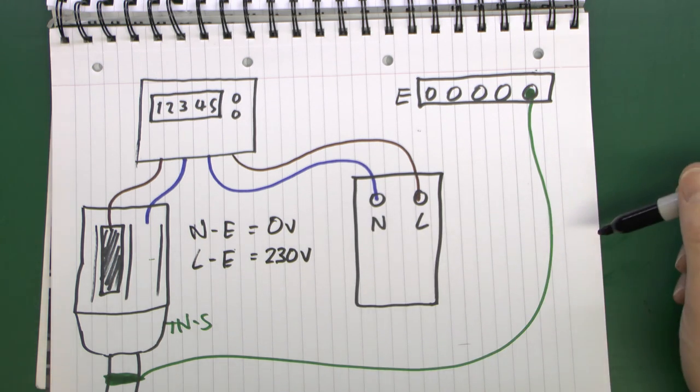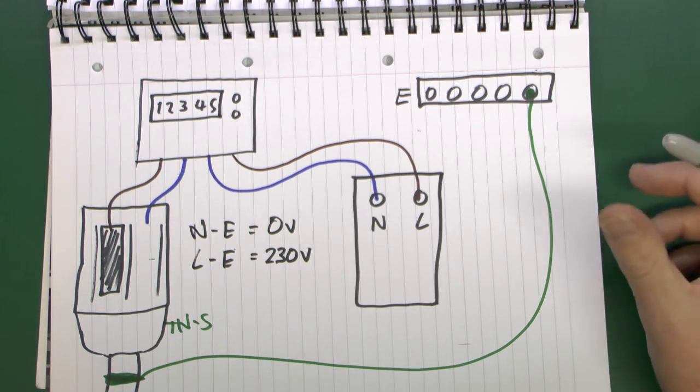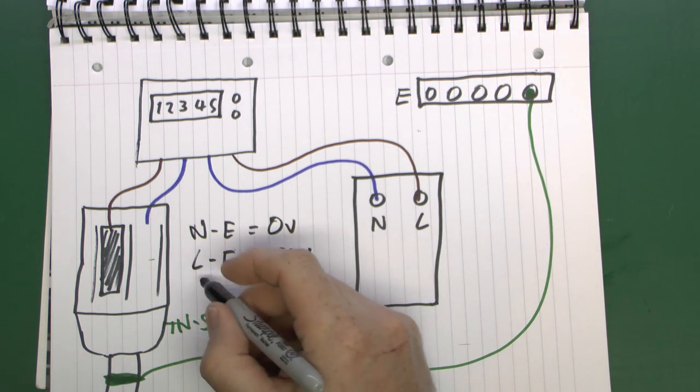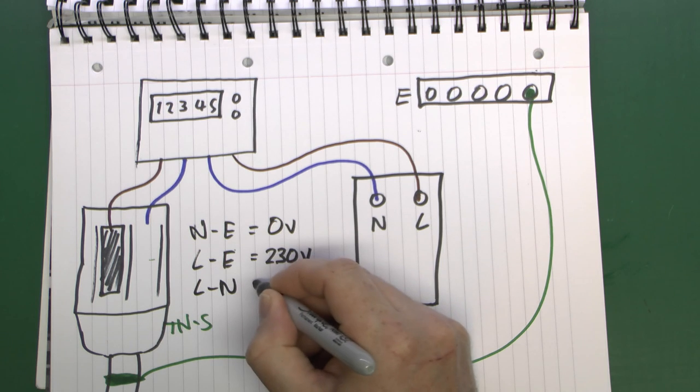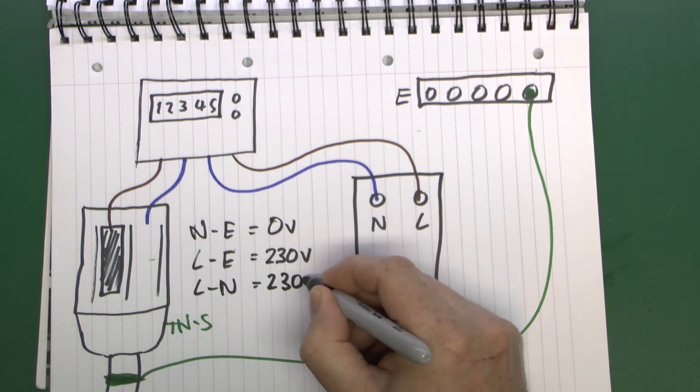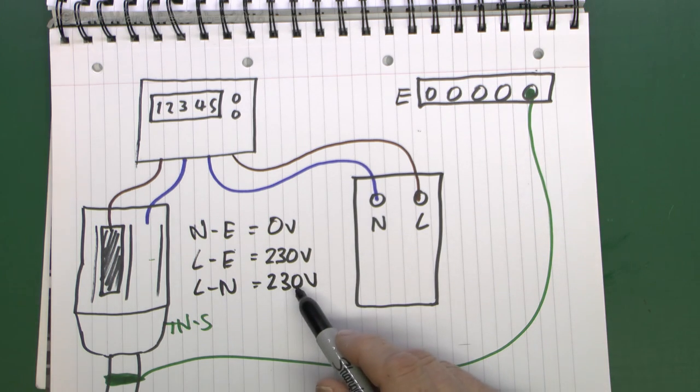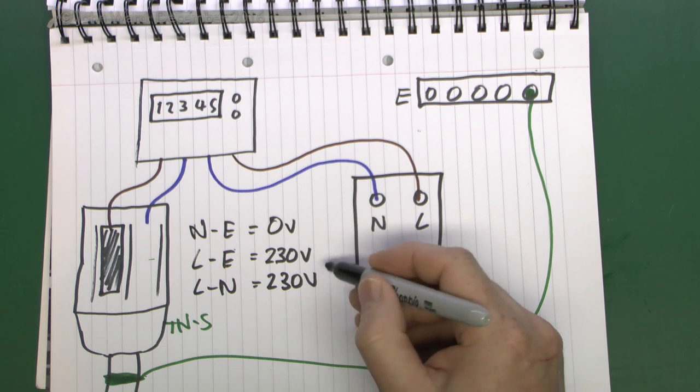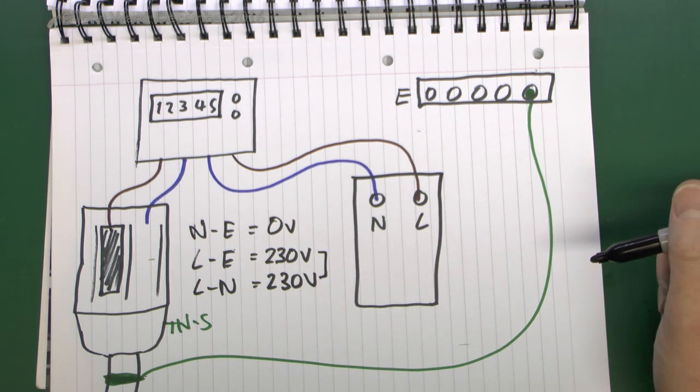In theory it could go up as high as 253, but generally that's rather too high so you might want to investigate why that was actually that high. And finally, if you check between line and neutral, then you should find pretty much the same voltage that you had there. That may vary slightly depending on the type of earth connection that you've got, but those two things should be substantially similar.